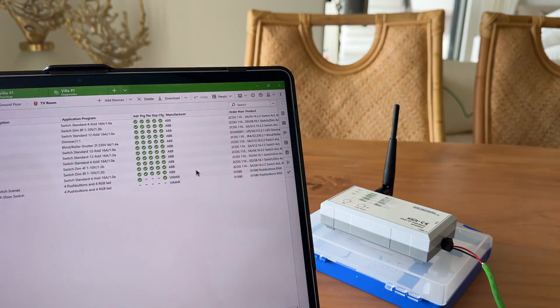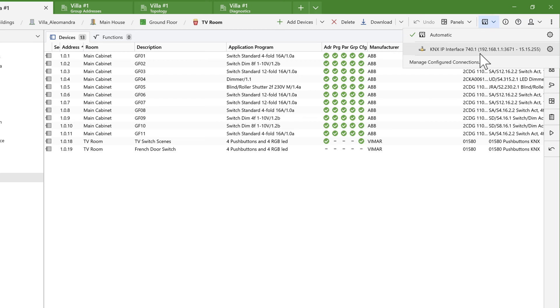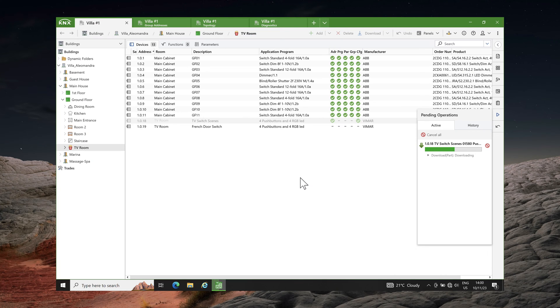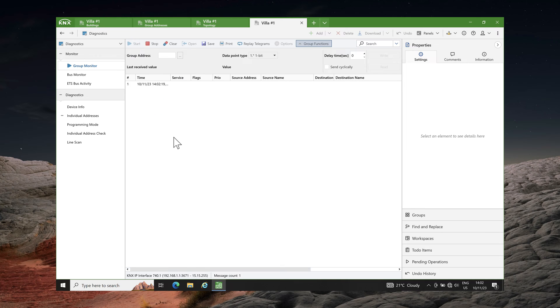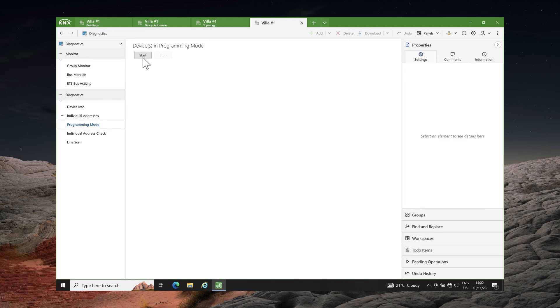Now let's move on to ETS6. Clicking on Connection Manager, you will notice that ETS6 has automatically discovered the KNX IP interface. I will select it and run some tests including partial download, download all, group monitor, device in programming mode, individual address check, and line scan.